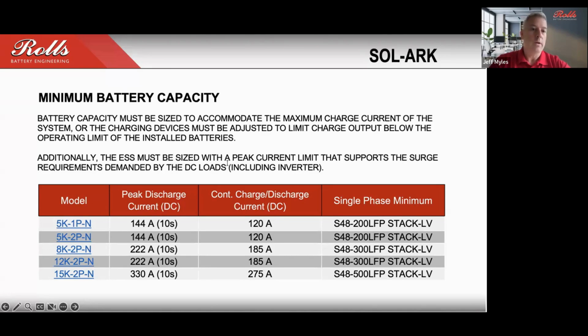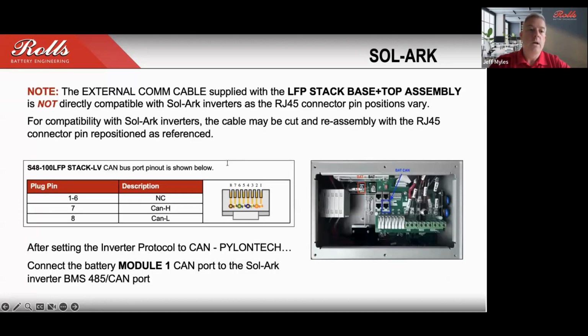And Sol-Ark is one of the inverter manufacturers where the straight through cable that's supplied will not work with their particular products. So what we've done is we've provided essentially a pinout that will show you what the order is for the cabling. And then again, as I mentioned, you will have some extra components that you can actually snip the wire and then realign that. They don't include a cable with the inverter that is directly compatible. The cable that they provide won't work on the battery side. So you essentially have to build an appropriate cable to be able to do that.